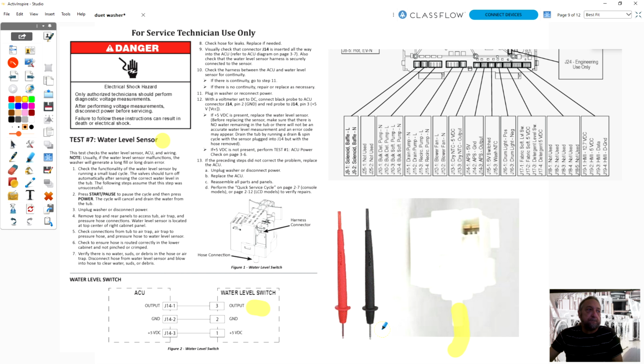I'd say from 1 to 2. On the water level switch, or 1 to 2 on the control board? On the control board, from J14.3 to J14.2. That is correct. You want to do it from volt DC to ground - the output is just communication between the two.